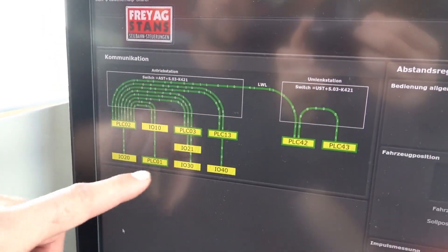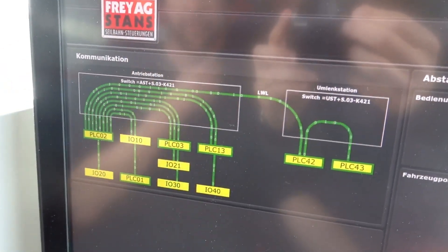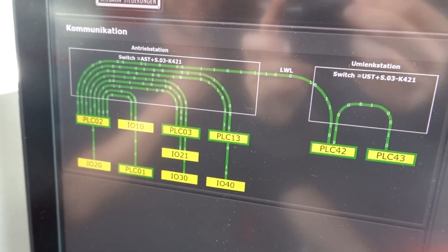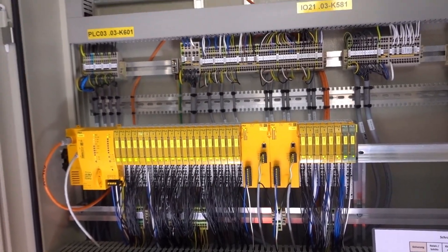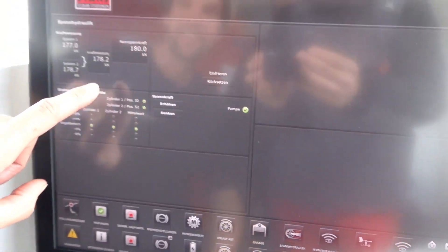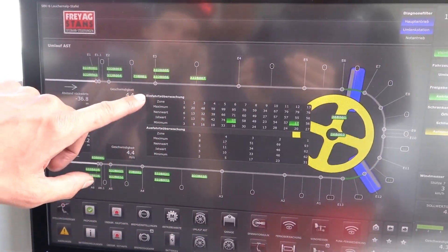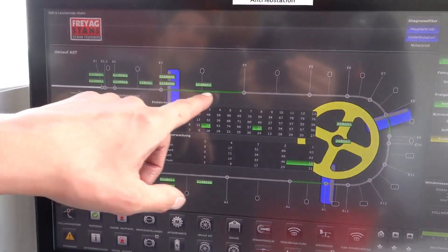The sensors are connected to several programmable logic controllers, or PLCs, that are interconnected through a complex bus system. This way, the thousands of cables connecting the sensors only need to go to the nearest PLC, in contrast to the older lift that had all wires going all the way to the central control system. The detail of the measurements is absolutely stunning. Here you can see the pressure in each of the two cylinders that keep the rope under tension. What was represented by the little green LEDs in the older ropeway — namely the position of each chair as it moves along the station — has given way to this virtual panel on a touchscreen.